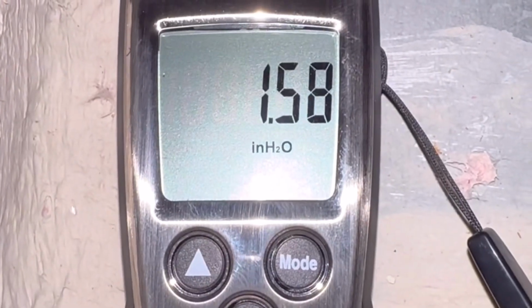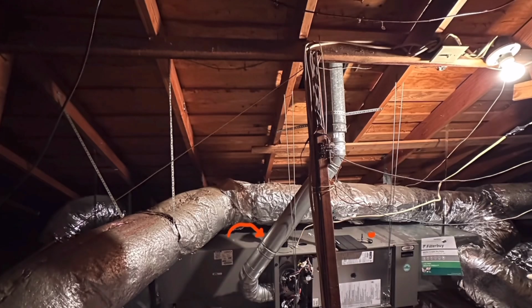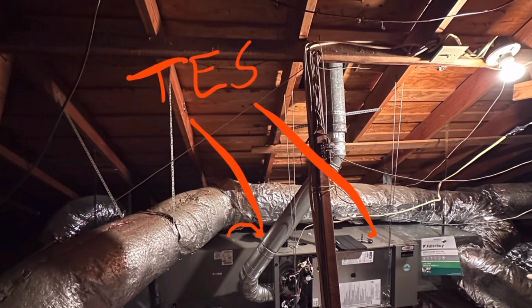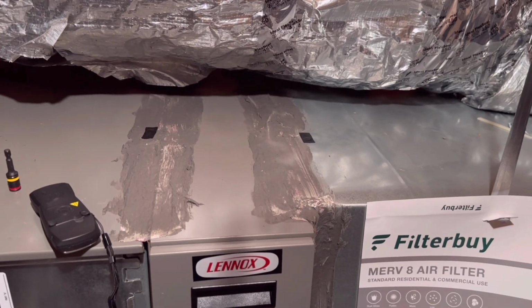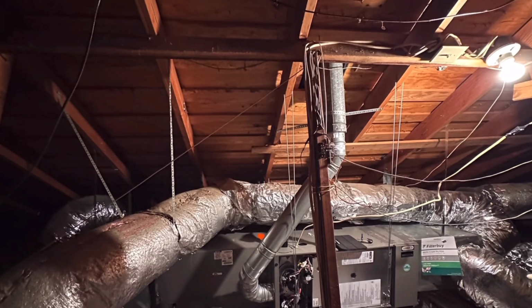For instance, we would check static pressure. If this is our blower and that's our heat exchanger, you'd check static pressure on this side of the filter and at the very end of the furnace just before the coil. To check pressure drop across your filter, you'd check from here to here. Pressure drop across your coil would be from here to here.